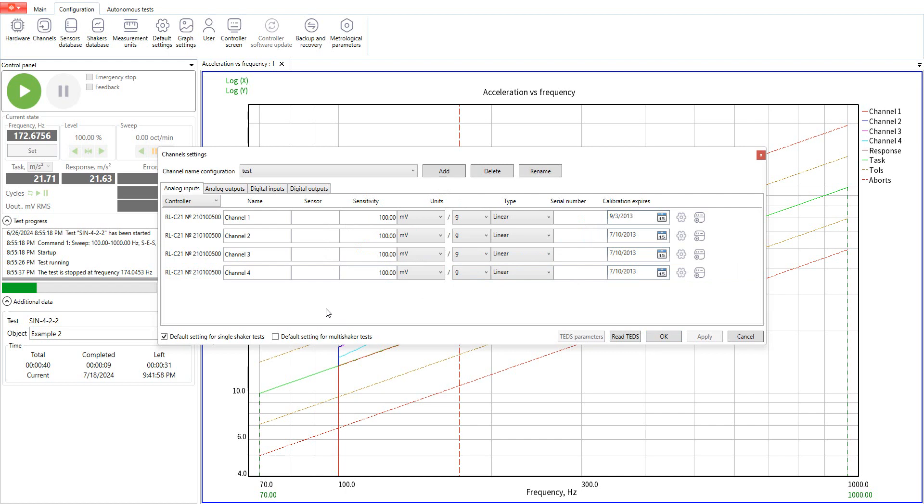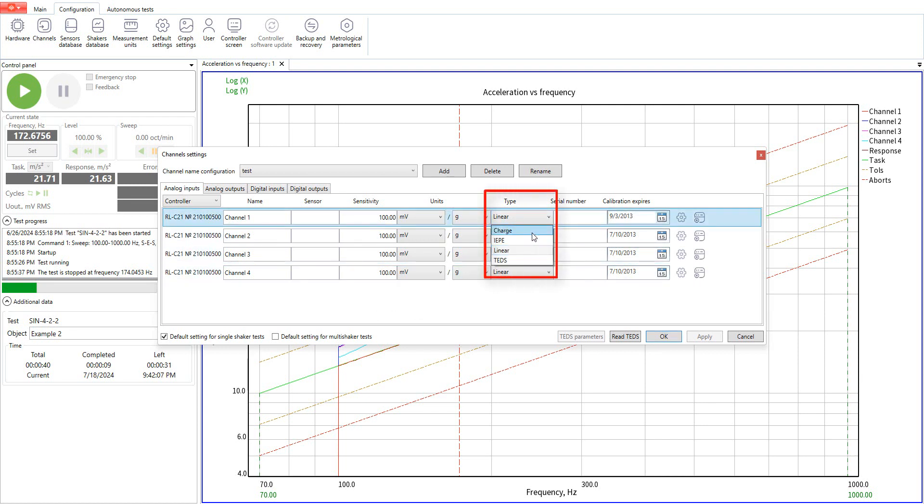Now we need to match the system input channels with the corresponding sensors. Now we need to choose the type of the connected sensor. It may be a charge sensor, an IEPE sensor, we can set up a linear input or choose a TEDS sensor.